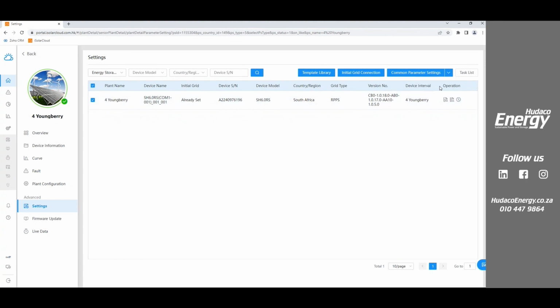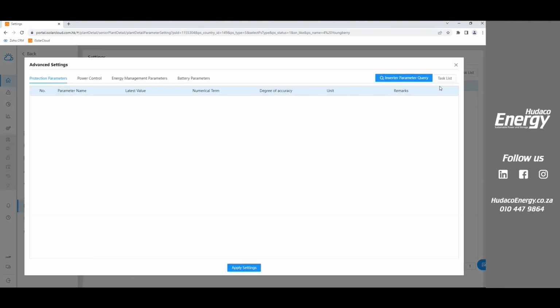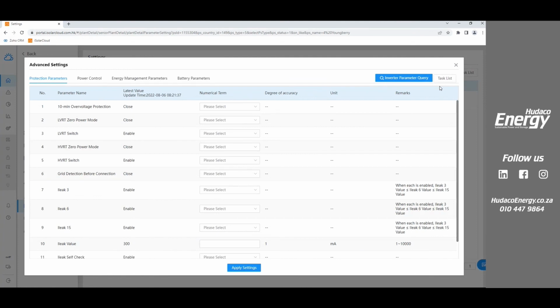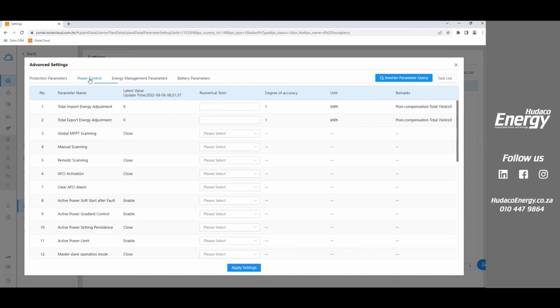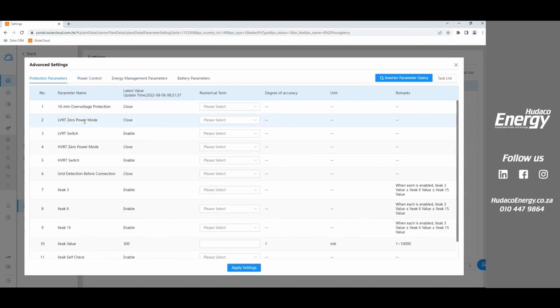At my house, the voltage from 2 Thursdays ago pushed up to 254. There was an issue on the transformer in the neighborhood. They did some repair work and it's pushed the voltage up, and I got all kinds of faults, lots and lots and lots of them. Protection parameters. So what we had to do is come through here and make some changes to it.